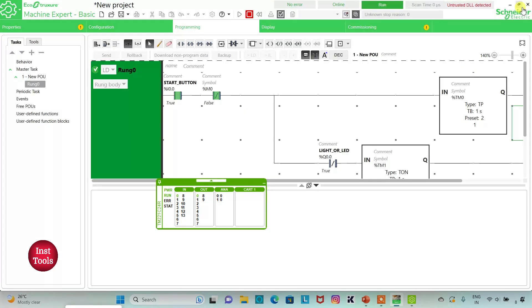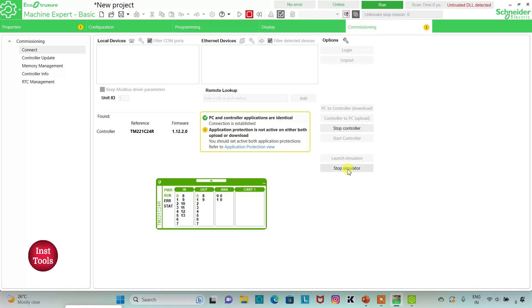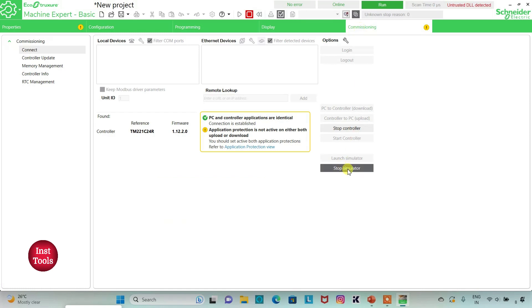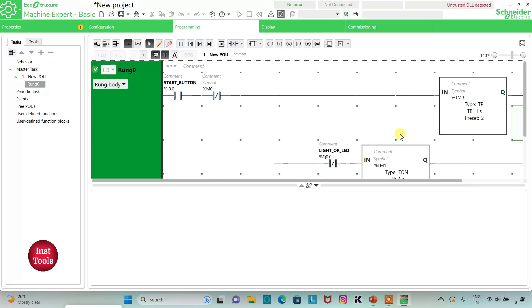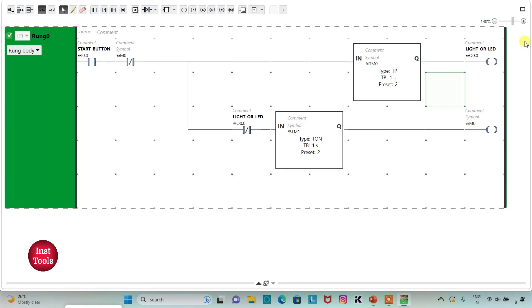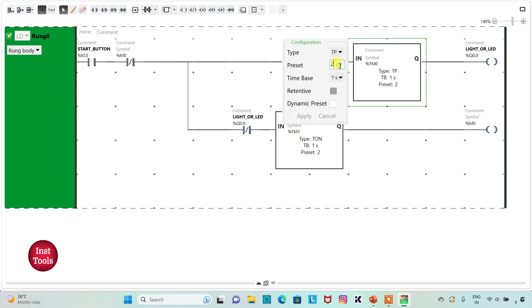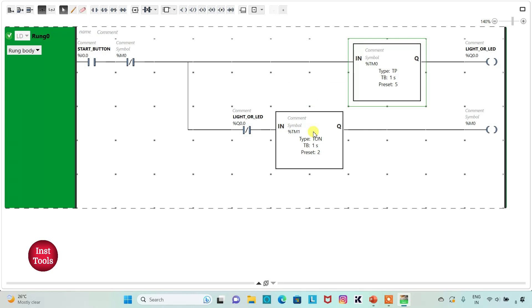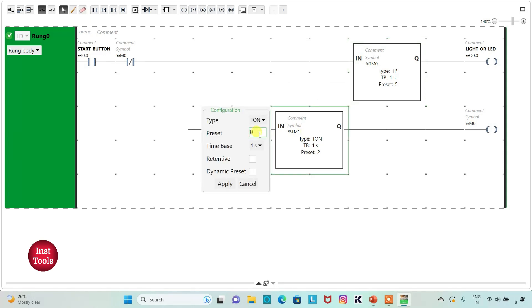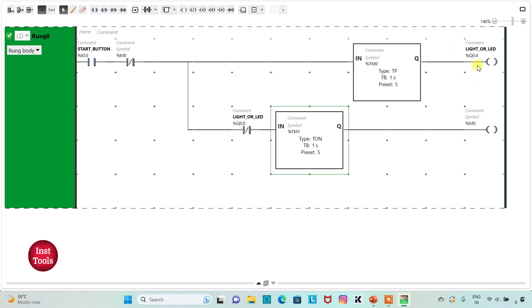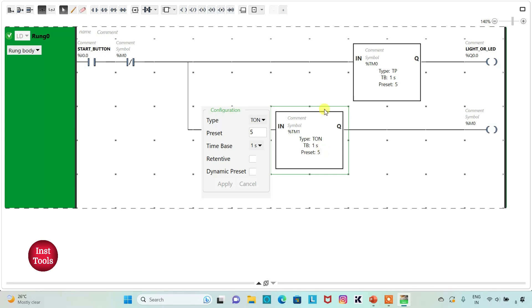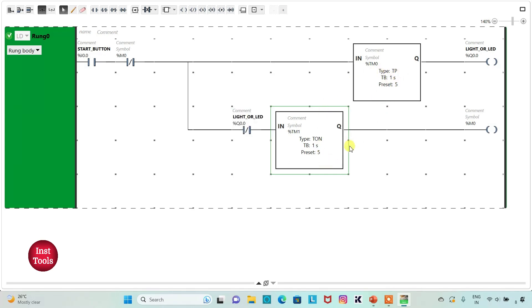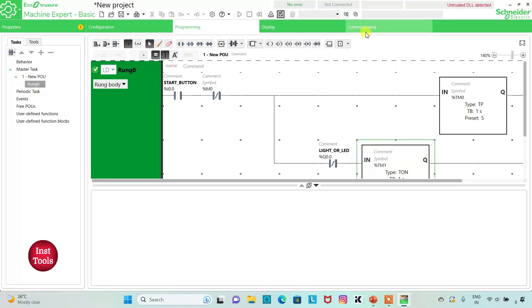I will exit full screen mode, go to Commissioning, and stop the simulator. Then I will go back to programming. We need to set the time interval to 5 seconds, so I will change the preset value of the TP timer to 5 and click Apply. Then I will change the TON preset value to 5 and click Apply. The LED will now be on for 5 seconds and off for 5 seconds, repeating the process.